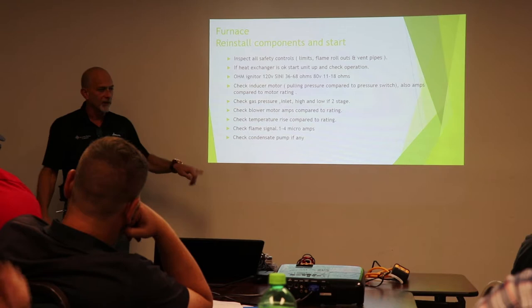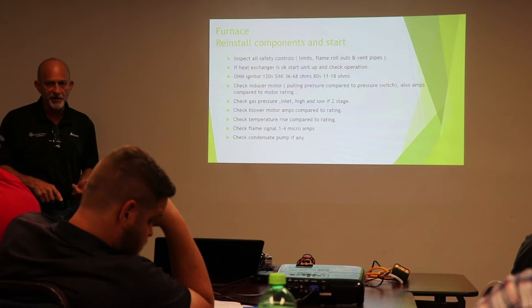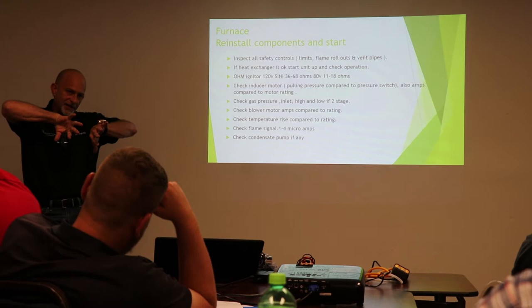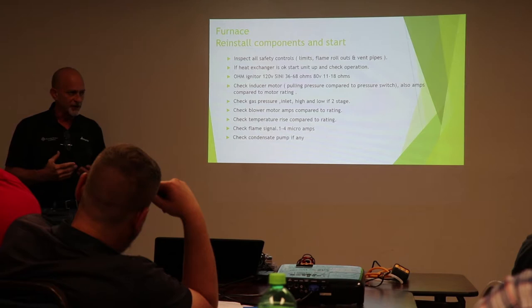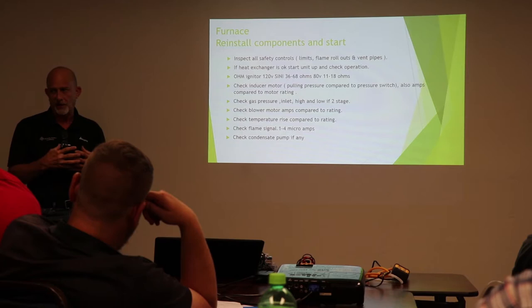If you use a file, a knife, heavy sandpaper, gritty sandpaper, what you're doing, first of all, is you're causing grooves in there. And what it does is takes that flame and scatters it around so you don't read a proper signal. And also with sandpaper, you're taking that grit and it stays on there and it burns on there. You coat it with that and now it won't sense at all.